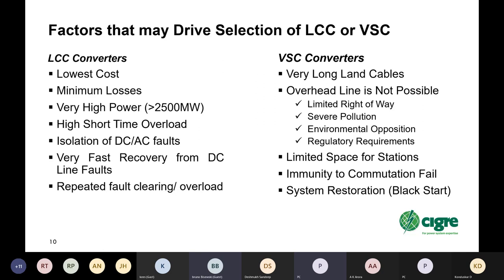LCC converters have typically quite a high capability for short time overload, which is important if you have a system where short time interruptions may mean that there's a stability problem, and then you need to bring the DC power back very fast and very hard to try and overcome that stability problem. Then the short time overload may be a very useful thing. It's really not available with VSC, which are typically operated right at their limit and have very limited, if any, overload unless you pay for it directly.